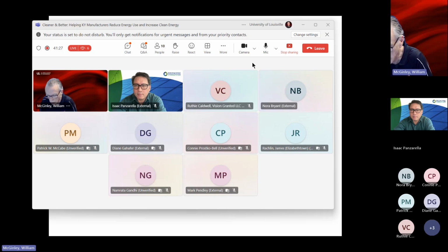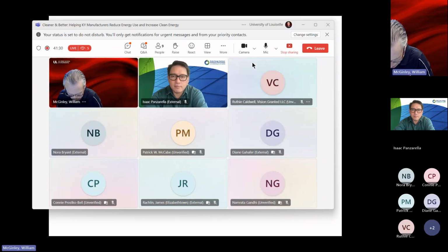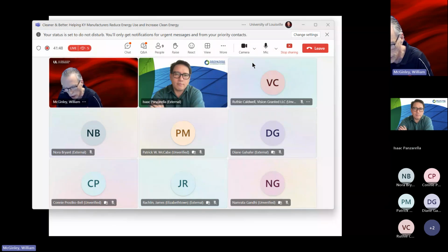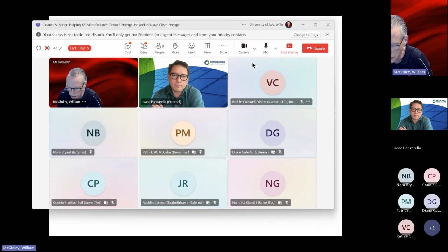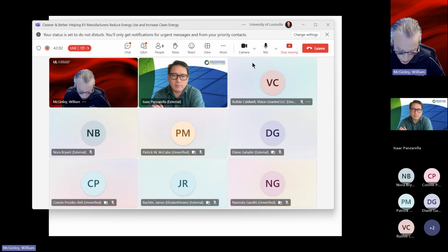Well, the one we're looking at designing will be direct air - there's a heat exchanger, and you bring the cooling air directly into it. For the water chilling, we just have a heat exchanger and a separate loop running the water through to pre-chill it. Only when we're augmenting it will we put in, in addition, what they call tempering the chill water - you'd add another heat exchanger in the line that becomes the evaporator coil for your chillers working on that particular loop.